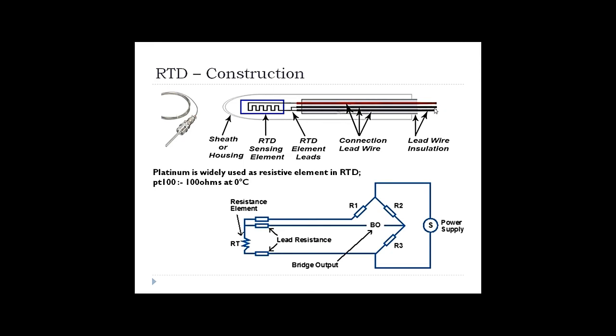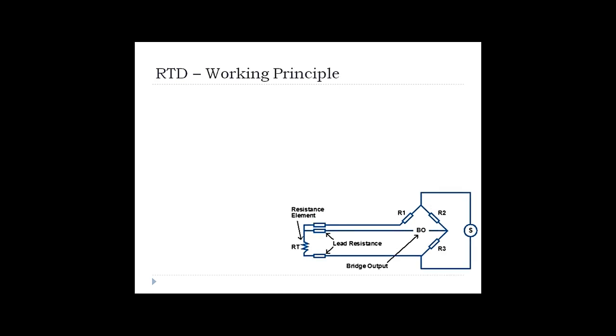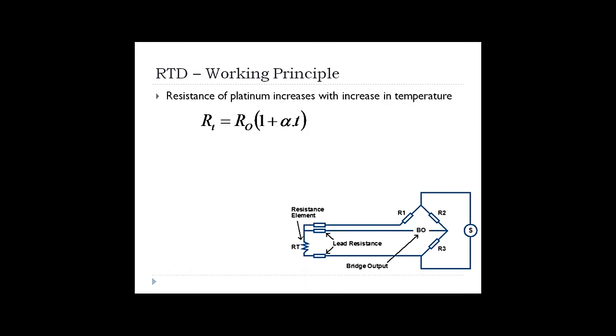The resistance is converted into electrical output very similarly to the strain gauge bridge circuit discussed in the last video. The RTD has three leads — current enters and flows through the RTD through R1, then it comes out. The RTD resistance is connected in a bridge circuit and this output is the final electrical output. The resistance of platinum increases with an increase in temperature, so RTD is used to measure temperature — as we increase heat supply, resistance also increases.